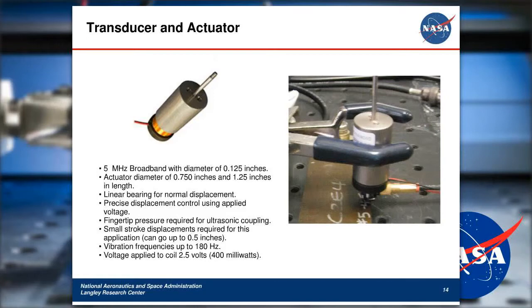Okay, so the actuator can be precisely controlled by applying a voltage to the coil, and so we can get stroke displacements up to 0.5 inches, but for this application, all we need is small stroke displacements. And then as we're coupling the energy to the sample, we're only using fingertip pressure. The vibration frequencies of the actuator can be anywhere around 160 to 180 hertz, and the duty cycle of that doesn't have to be 50%, but it can be less than that, anywhere from 15% to 30% duty cycle. The voltage applied to the coil is about 2.5 volts, and that provides about 400 milliwatts of power to the actuator.